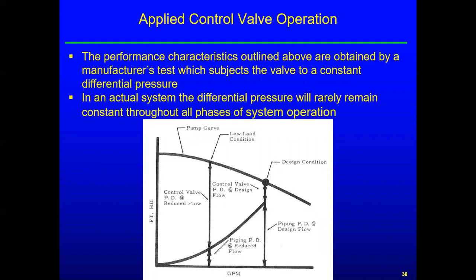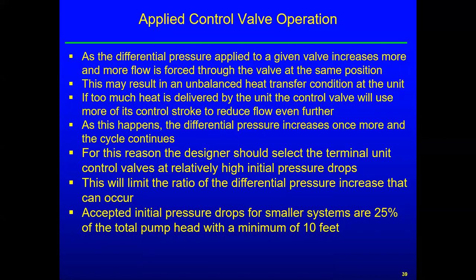So that's kind of the explanation of this slide. Okay, so still under control valve operation, as differential pressure applied to a given valve increases, more and more flow is forced through the valve at the same position. So in other words, this would be kind of like a laboratory setting or something. But if you took a valve and you put it, whatever position it was in, could be 100%, could be 50%. As I apply more pressure, upstream pressure, I'm going to push more flow through the valve. So that's what the first point is saying. That's, I think, fairly obvious. This may result in unbalanced heat transfer condition at the unit.